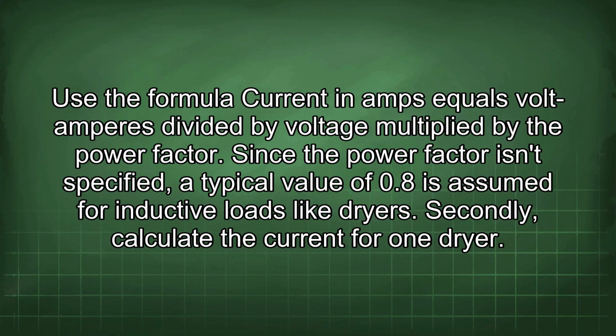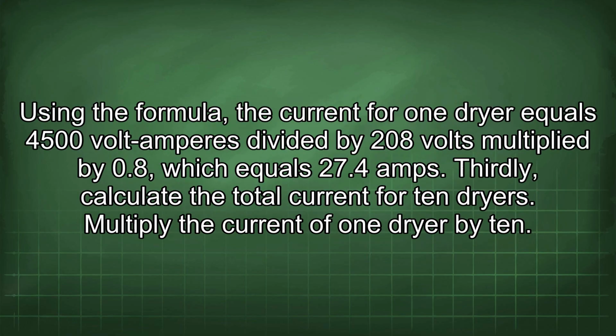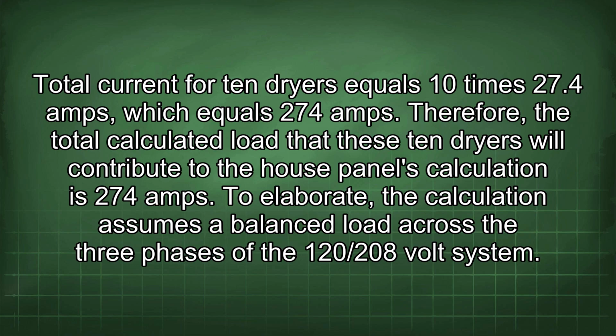Secondly, calculate the current for one dryer. Using the formula, the current for one dryer equals 4,500 volt-amperes divided by 208 volts multiplied by 0.8, which equals 27.4 amps. Thirdly, calculate the total current for 10 dryers. Multiply the current of one dryer by 10. Total current for 10 dryers equals 10 times 27.4 amps, which equals 274 amps. Therefore, the total calculated load that these 10 dryers will contribute to the house panel's calculation is 274 amps.